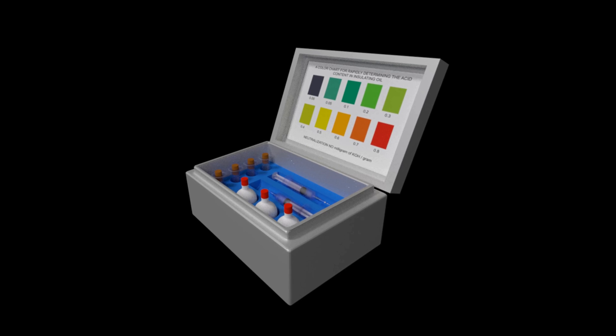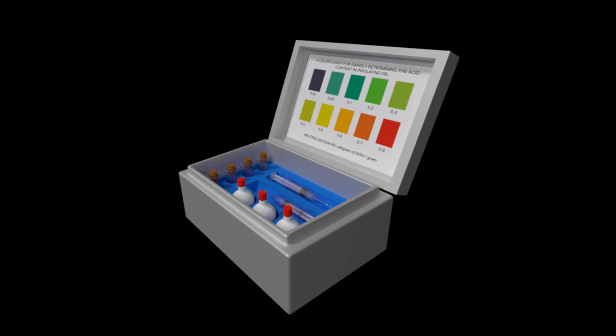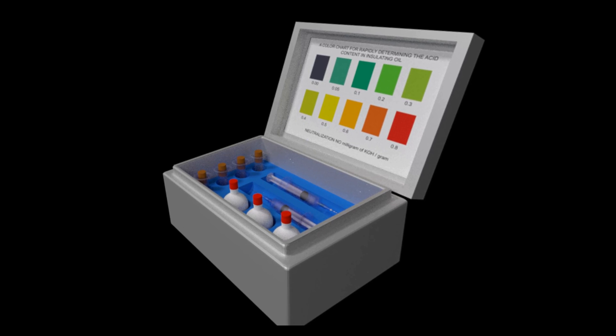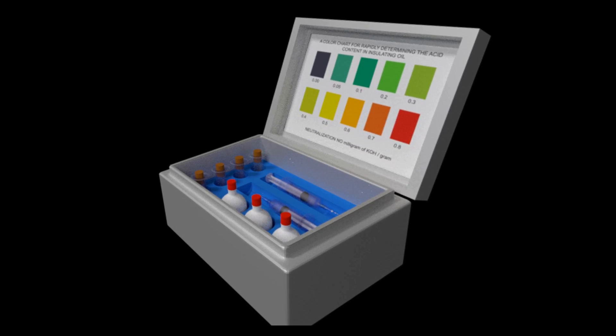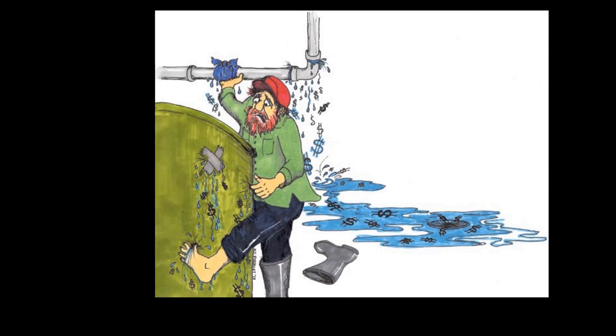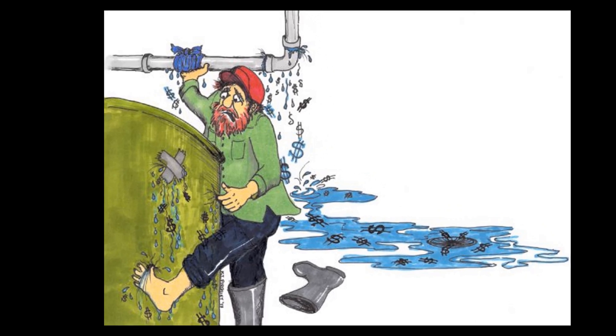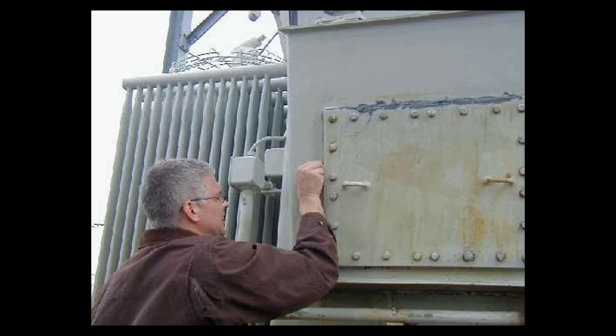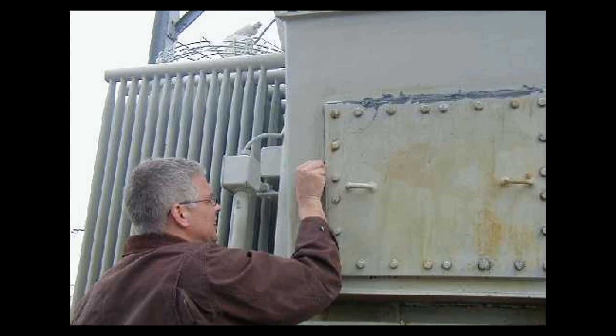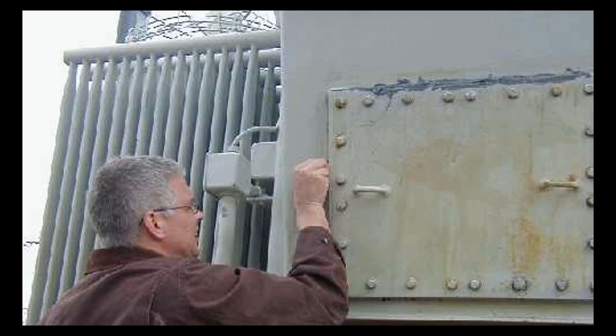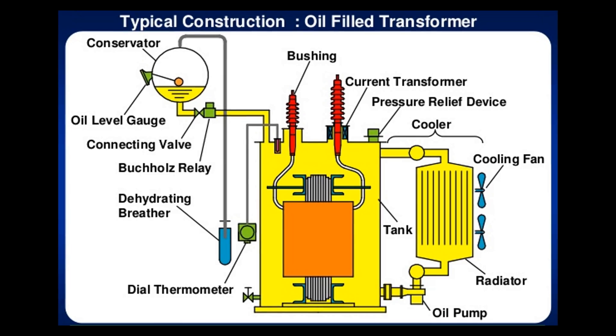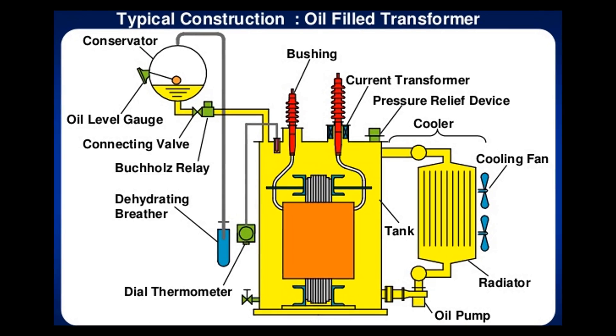Transformer acidity test. Insulating oil in the transformer may occasionally come into contact with air — this may happen during opening of any blanking or due to leakage in the oil tanks or in associated pipelines. Because of that, oxidation reactions in the transformer oil take place.